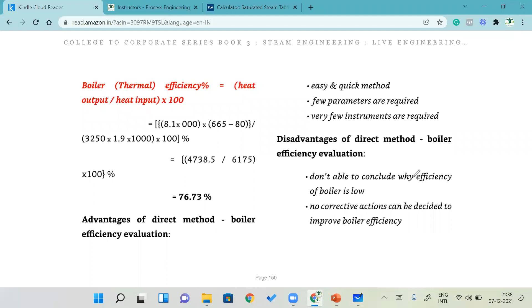In the indirect method, there are many heat losses. We have 100, and from that 100 we subtract many heat losses. First, the heat losses through dry flue gases. As I told you, initially the air is coming, and the flue gases that are leaving the boiler are at higher temperatures. That means they are taking some amount of heat, and that is not useful for you. That is inefficiency. That is where you are losing some efficiency.